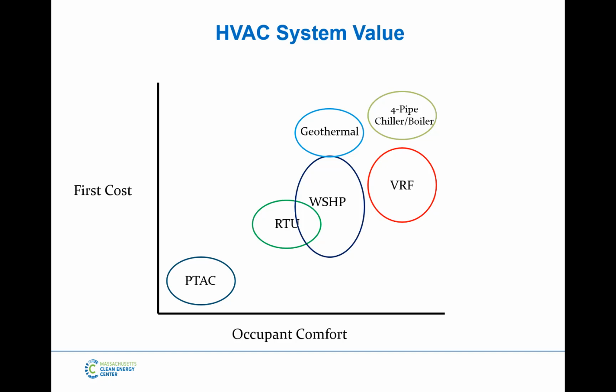But really what I'm thinking to use this for is if someone gives you two options between PTAC and a VRF system and they cost the same, look into why that's happening. That doesn't make sense. Similarly, if someone's comparing a VRF system to a 4-pipe chiller boiler and the VRF system is significantly more expensive, you're also going to want to look into that and find out why the difference is there. Did they budget it correctly? Did they price it correctly? Was there something different in the design that made them fundamentally different? Just a general rule of thumb here.